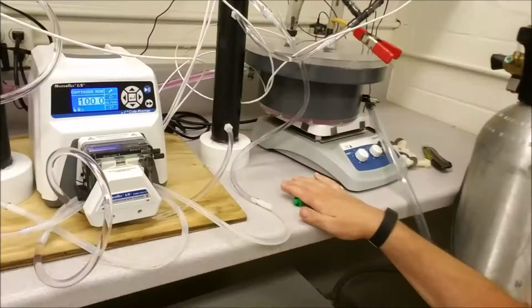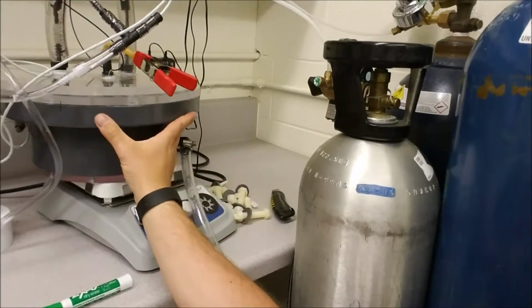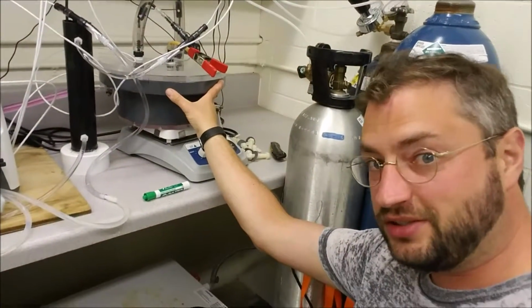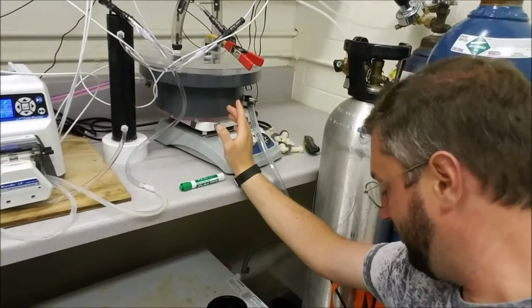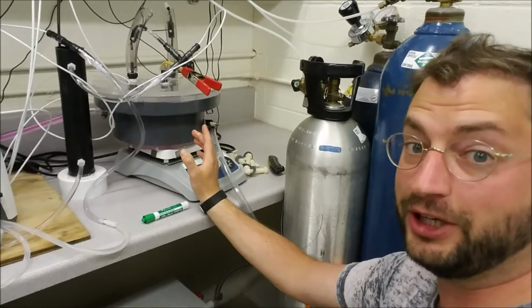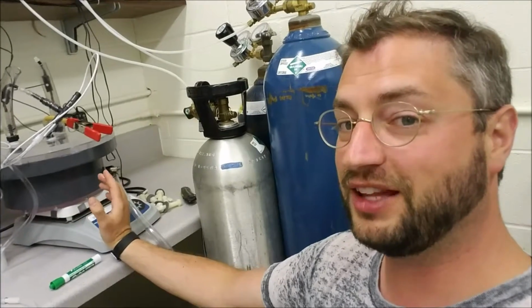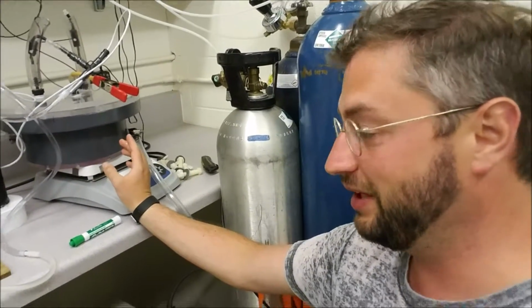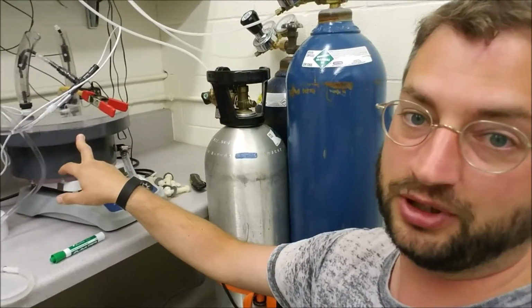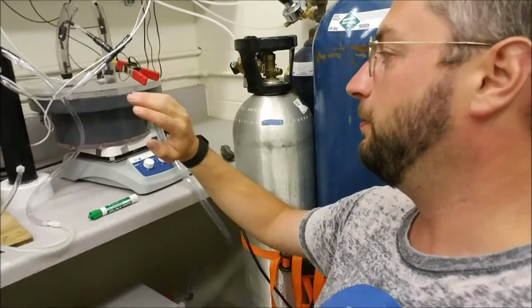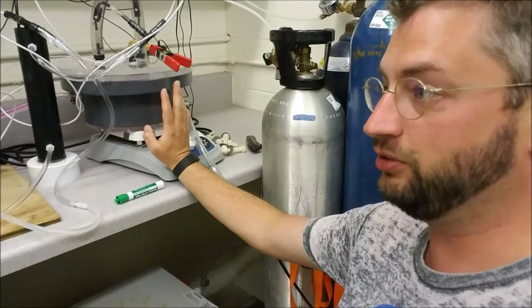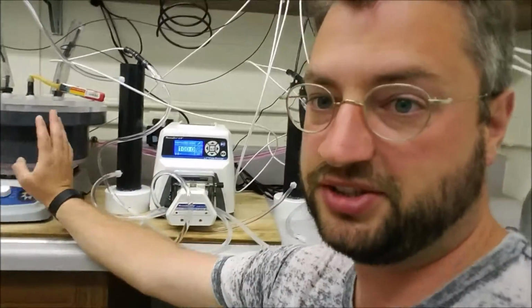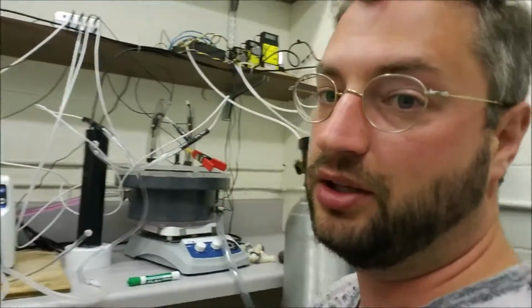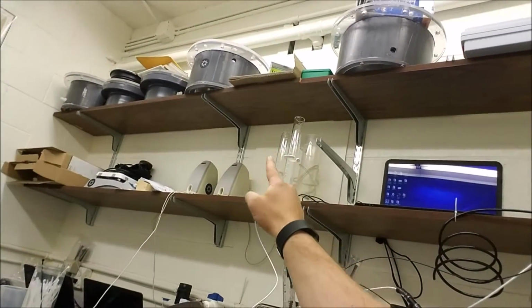However, the problem I ran into is that it comes up here, and then this water jacket leaks. So it started spewing antifreeze everywhere. That was actually a problem I encountered last year. We spent a lot of time correcting it, and now I'm having it again. Which essentially means we're going to have to take this respirometer off, tear it apart, redo all the seals in it, and then put it back together, let it dry, and hope it works. I'm going to test this one tomorrow and see if that one's doing the same thing. I have a handful of other respirometers up there, and maybe I can use some of them.